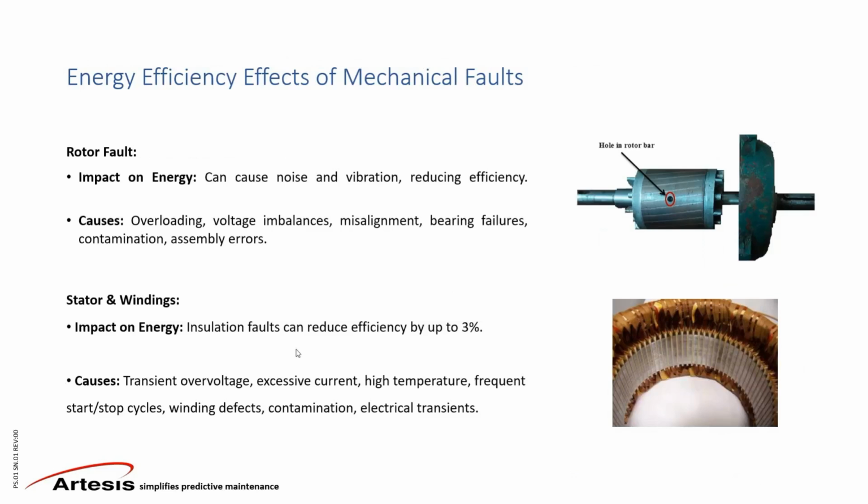Of course, if you have a broken rotor bar, you will have dynamic or static eccentricity, which will affect the performance, the torque of the motor, and of course that will reduce the efficiency of the motor.